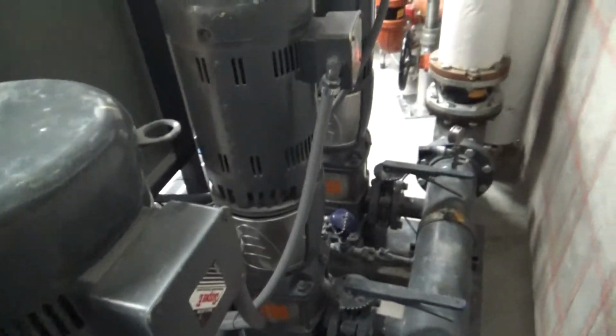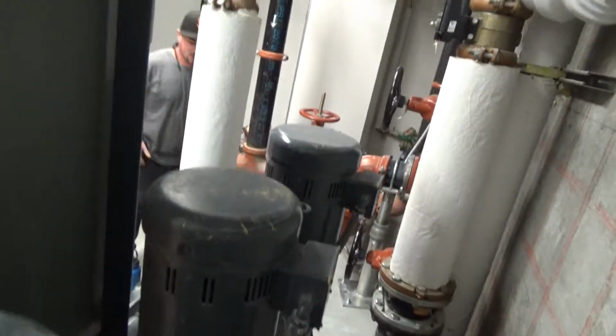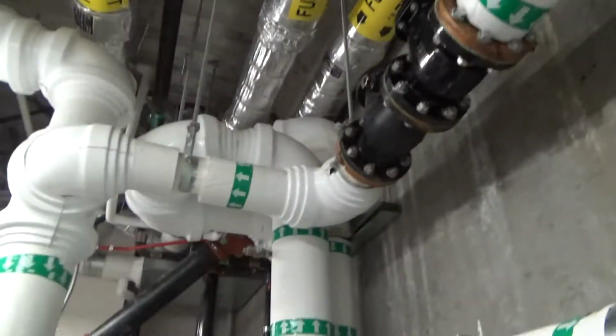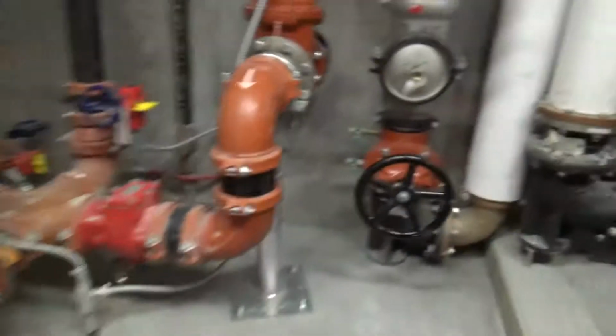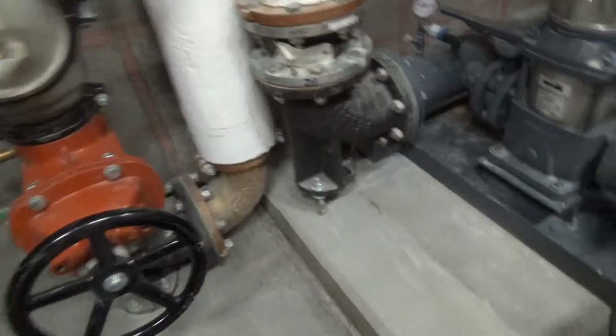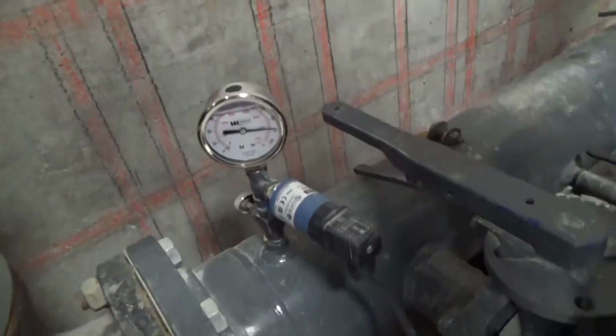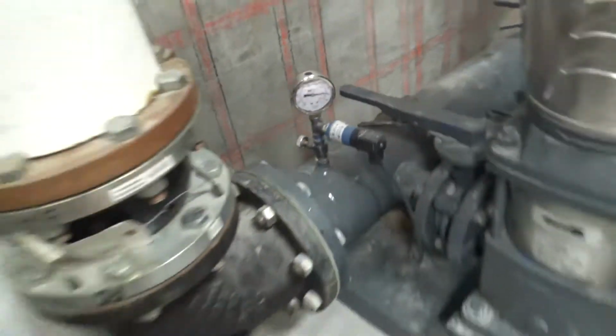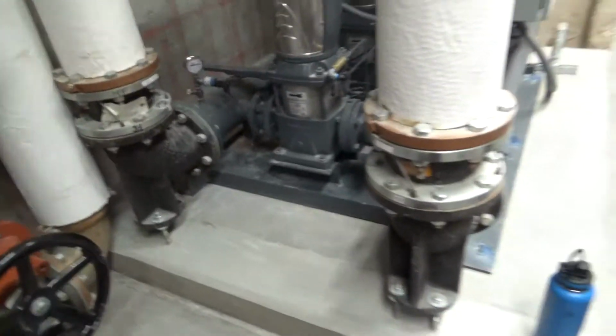But what we're doing here is we're taking city water, for whatever pressure we have it coming in at, which you guys are getting about 88 psi, which is normal for the city. The city usually has pretty good pressure. And we are boosting it up to a higher pressure to get it up to the top floors and their domestic hot water system up there and all that.